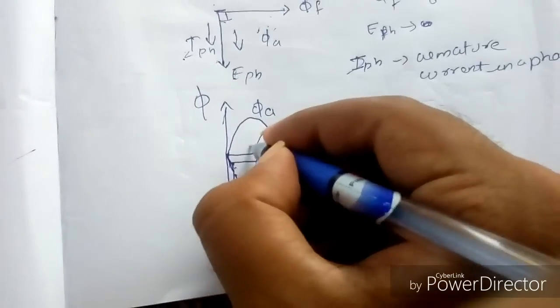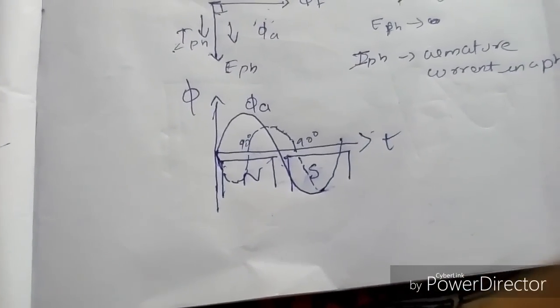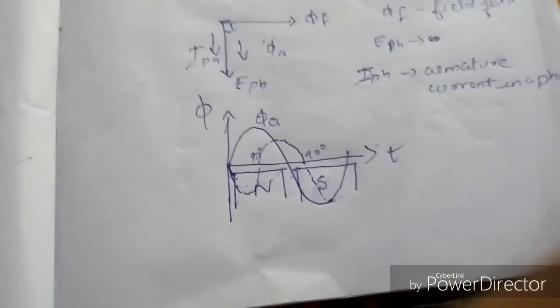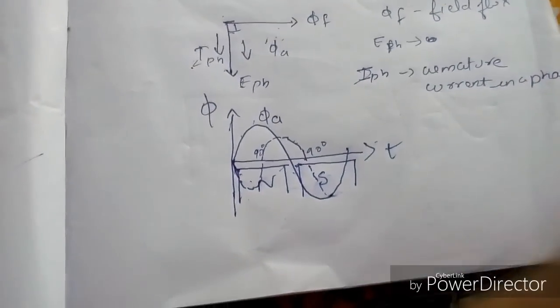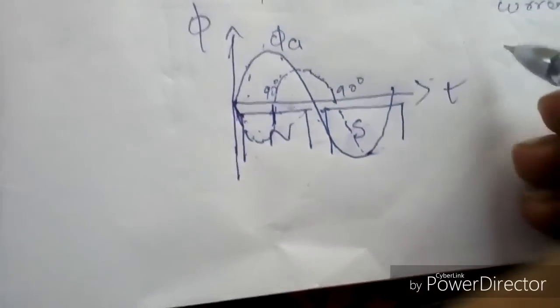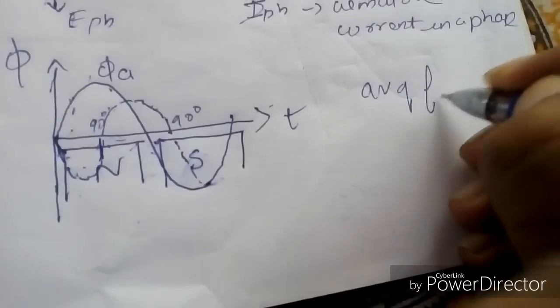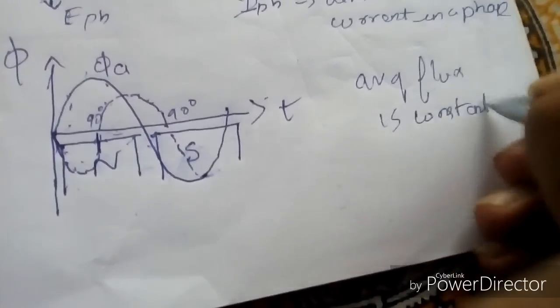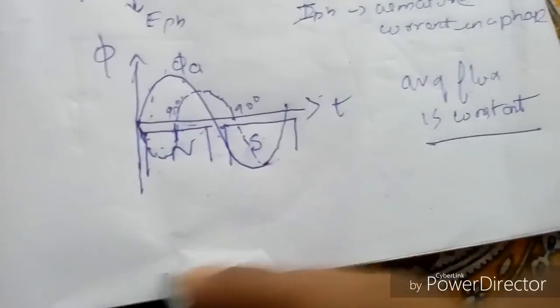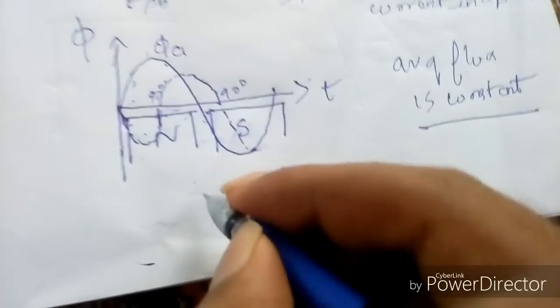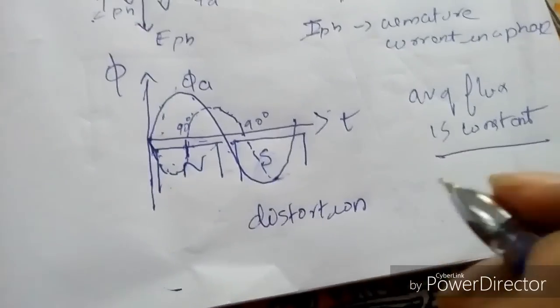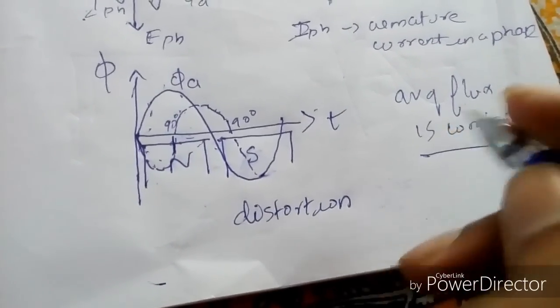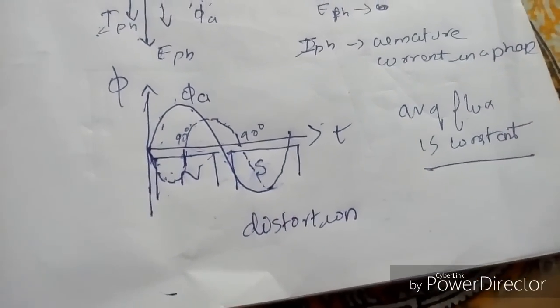The phase difference is 90 degrees. On the left side of the north pole, both the armature flux and field flux oppose each other. But on the right side, these two fluxes assist each other, and on the left side these two fluxes oppose. So the average flux is constant — the flux is not reduced. But there is a distortion in the flux distribution.